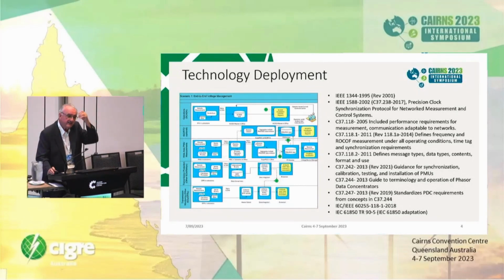The issue remains, how do you integrate all of these samples and eventually measurements into the control room, for example? How do you put them into the SCADA database and applications in the control room? It doesn't have to go to the control room, incidentally. You will see that from some other applications. It can be a special protection system that just takes inputs and issues outputs to particular breakers, and never goes to the control center per se.